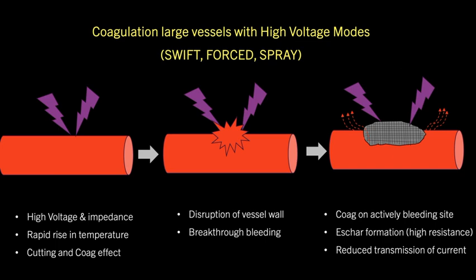As can be seen here, high voltage modes are associated with rapid rise in temperature, which results in both cutting and coagulation effect. This results in disruption of vessel wall and breakthrough bleeding. Coagulation on an actively bleeding site results in eschar formation and high resistance, which results in reduced transmission of current and reduced effectiveness of coagulation.